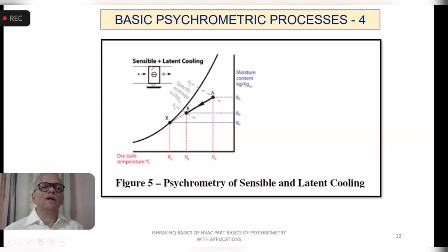That is the apparatus. There you see the symbol with minus, meaning you have heat removal here. It is also showing a tray and a few drops falling. The indication is that you are removing moisture, which is getting condensed over this cooling coil and dropping out as condensate. So you get out air that is cooled, with sensible heat removed, as well as dehumidified, with latent heat or moisture content removed. And that's your leaving point.